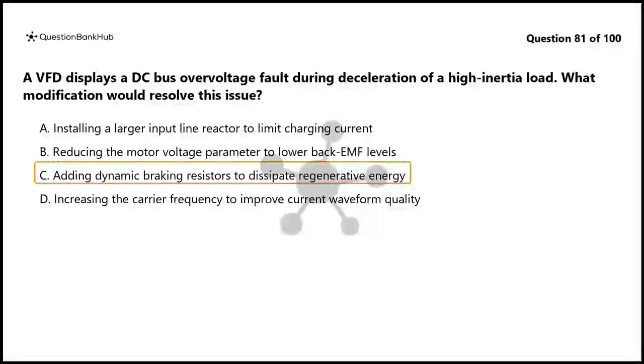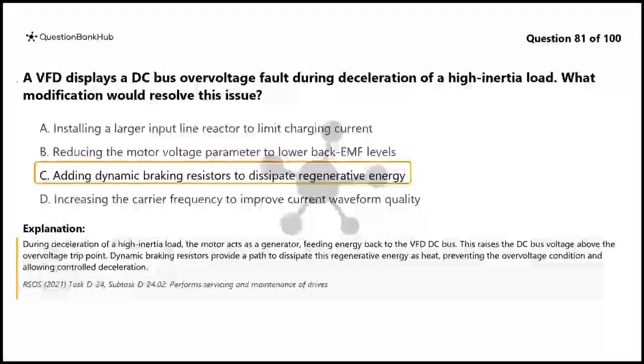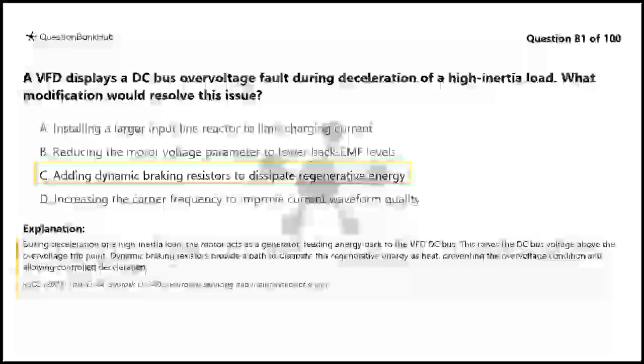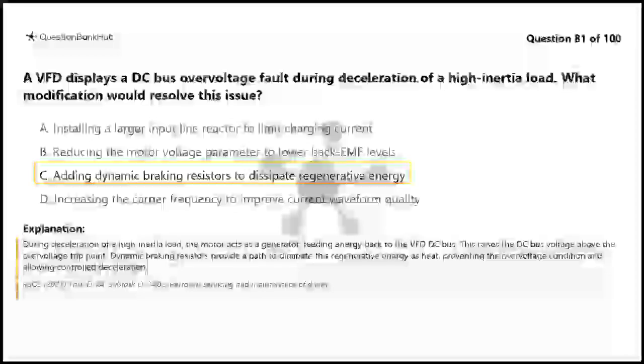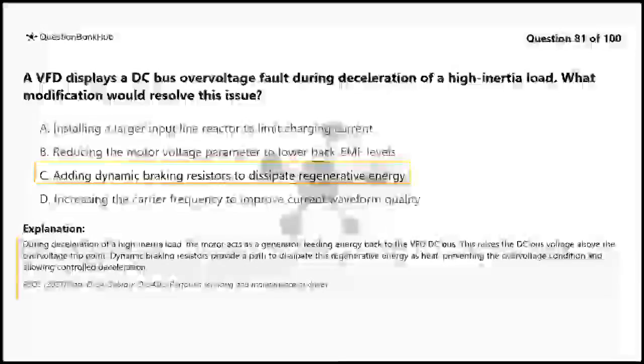The correct answer is C. Adding dynamic braking resistors to dissipate regenerative energy. During deceleration of a high inertia load, the motor acts as a generator, feeding energy back to the VFD DC bus. This raises the DC bus voltage above the overvoltage trip point. Dynamic braking resistors provide a path to dissipate this regenerative energy as heat, preventing the overvoltage condition and allowing controlled deceleration.